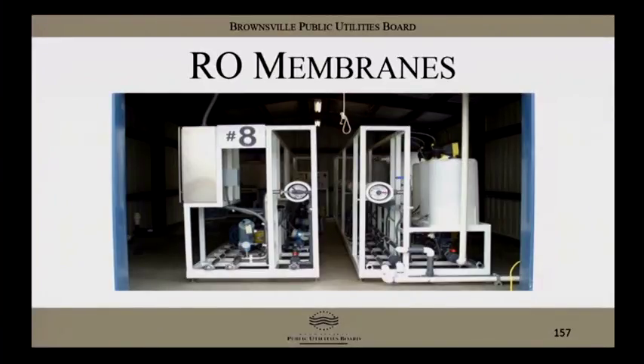This is a picture of our RO units that were tested. On the left, we had a Toray seawater RO membrane system. On the right, same thing, but it was a FilmTec system. And those we ran, what we found was the membranes, the seawater membranes, were capable of producing a very high quality water that could produce the potable standards that we were trying to achieve.